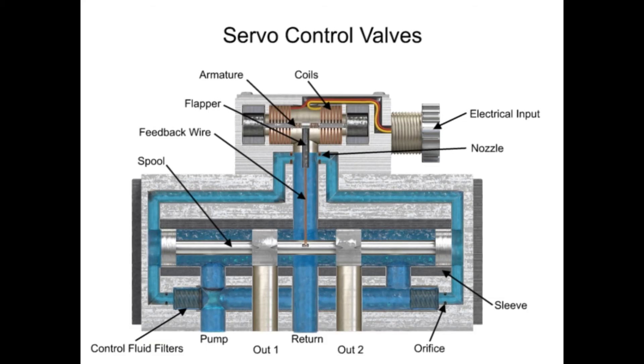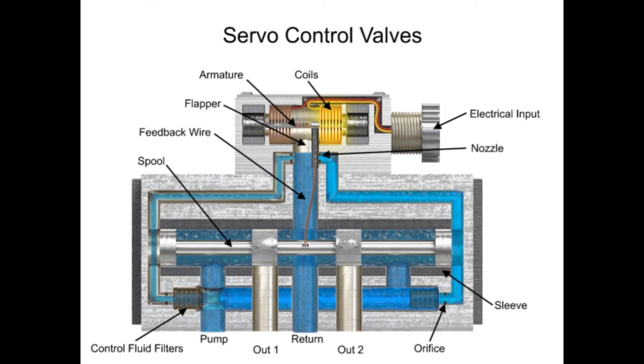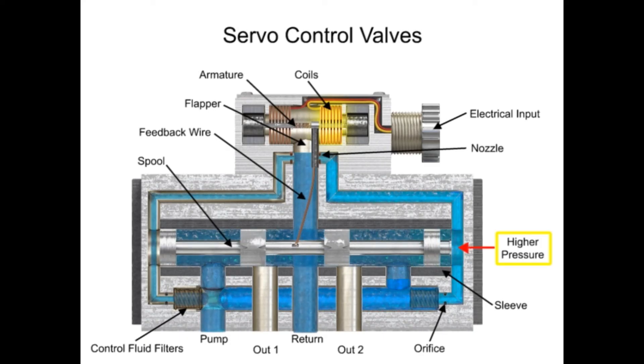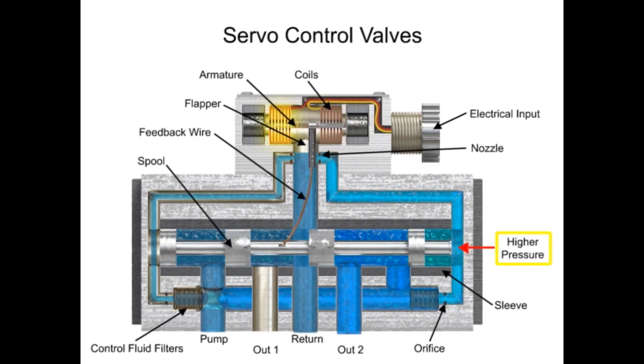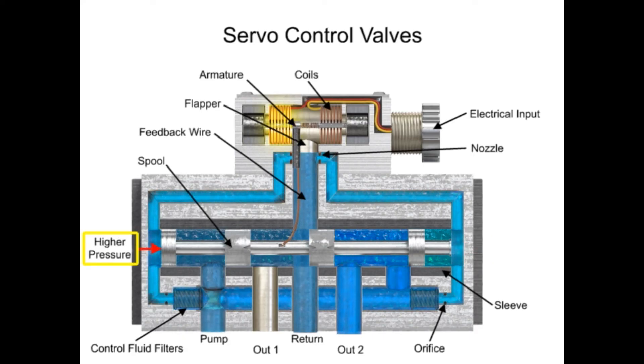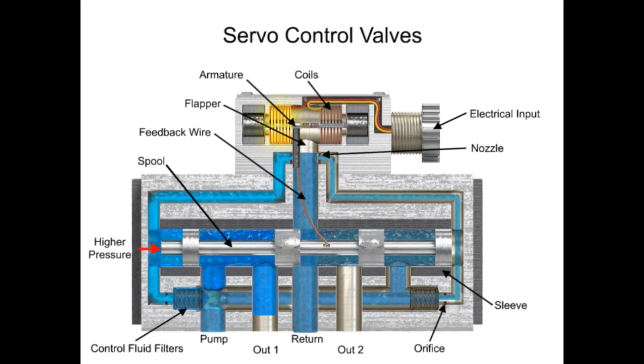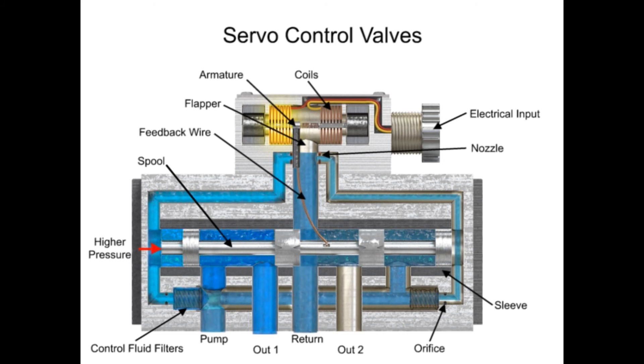When the torque motor coils receive a current signal, the armature rotates clockwise or counterclockwise and pushes the flapper closer to one nozzle and farther away from the opposite one. This allows pressure to increase at one end of the spool and decrease at the other. The spool then starts to move away from the higher pressure. If the armature turns clockwise, pressure builds on the left end of the spool and it moves to the right. With these very accurate feedback devices and a fast-response servo valve, an actuator's position, speed, and/or force can be repeatedly established within an extremely close range. Electronics provides the accuracy while hydraulics provides the force via a super-responsive servo valve.